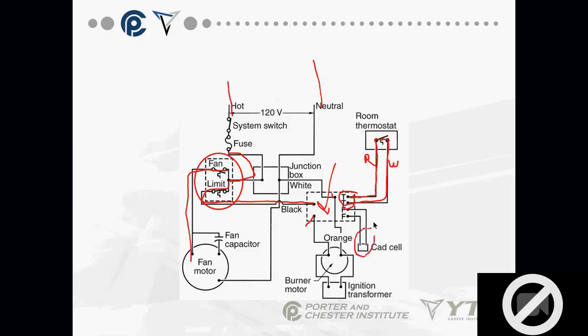CAD cell, okay, connects to the primary control. There's two terminals marked F and F. That's where my CAD cell connects. I don't know what F stands for, but that's where my CAD cell connects. It's always yellow wire, too. Okay? Primary control contains everything, all the relays, everything I need to make the burner motor run and the ignition transformer work, and all the cycling is in that primary control.